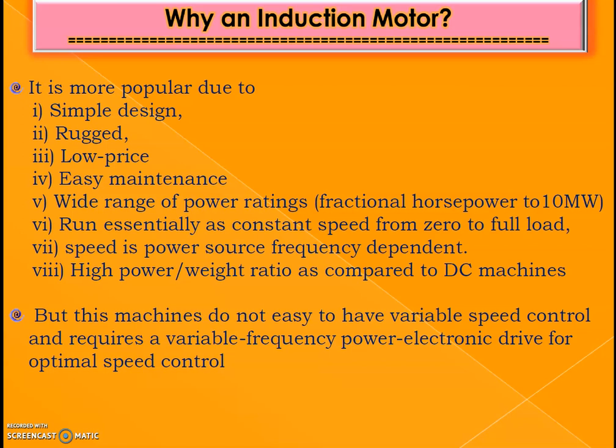It runs essentially at constant speed — from zero to full load the speed regulation is almost zero. The speed is dependent on the power source frequency, so speed is a function of the supply frequency. It also has a high power-to-weight ratio compared to DC machines — for the same power, the DC machine has a larger weight than the induction motor.